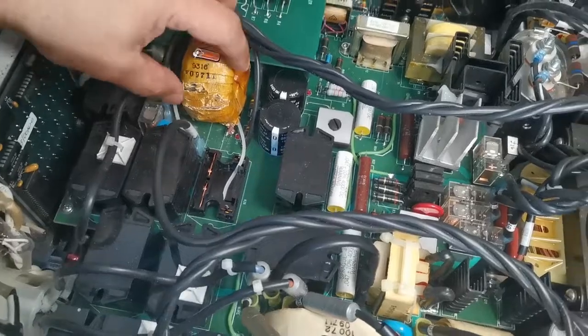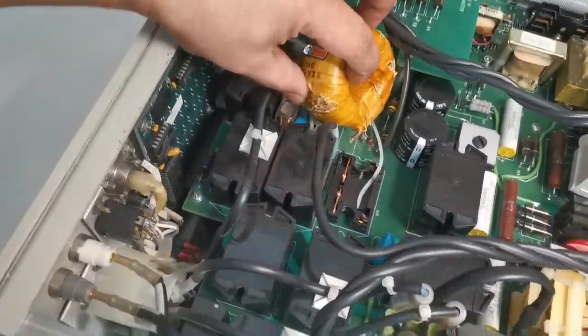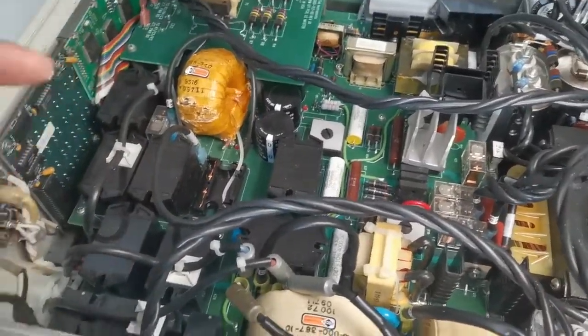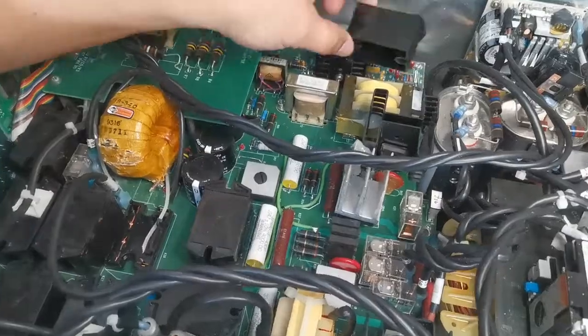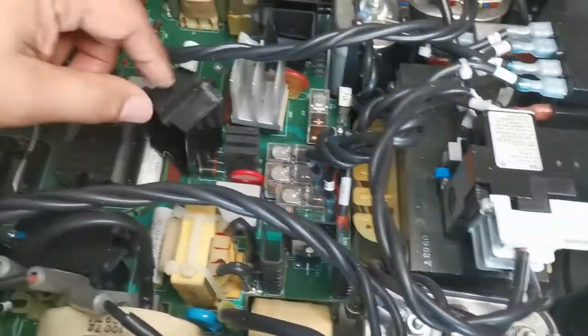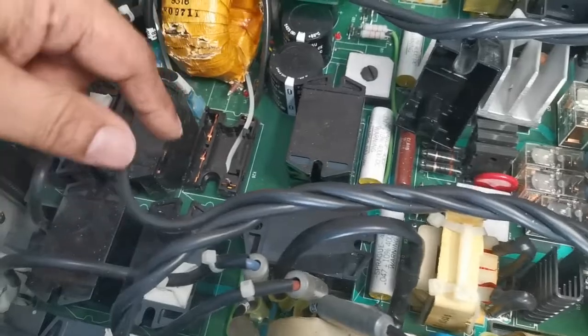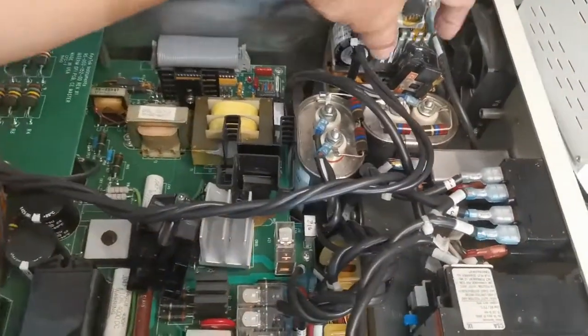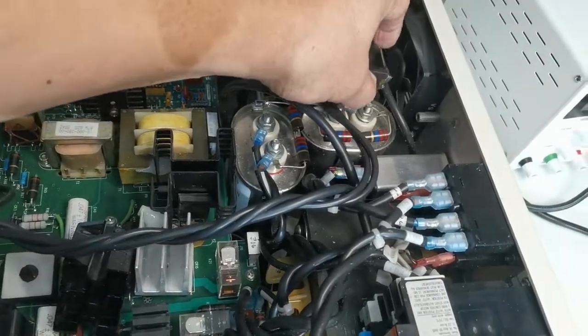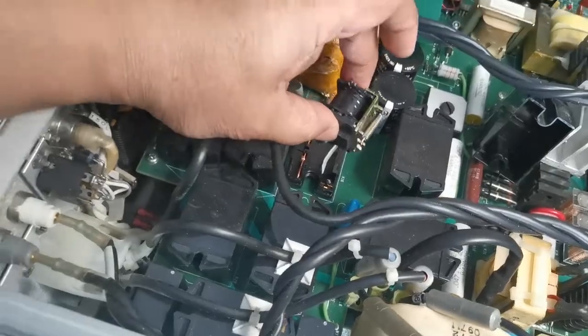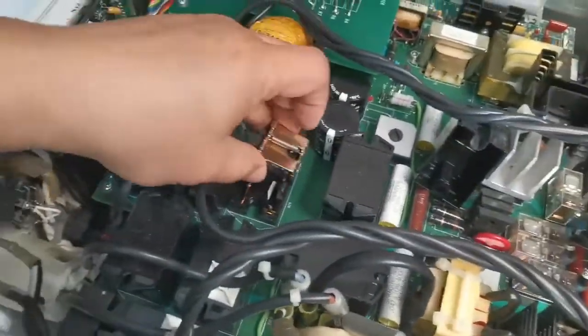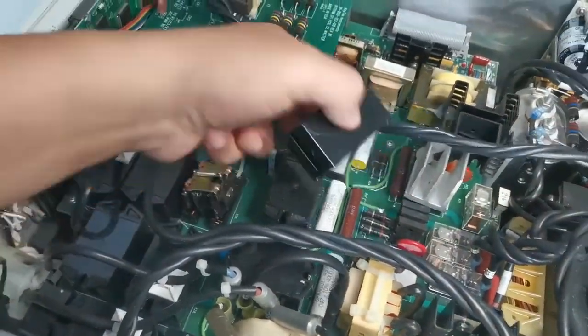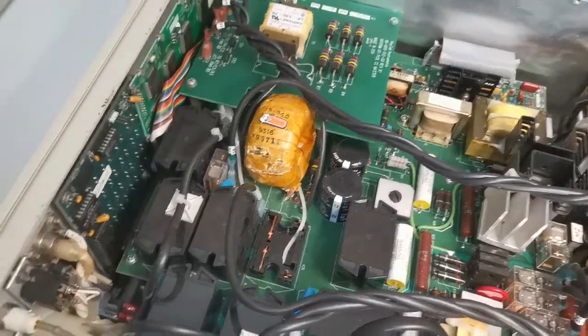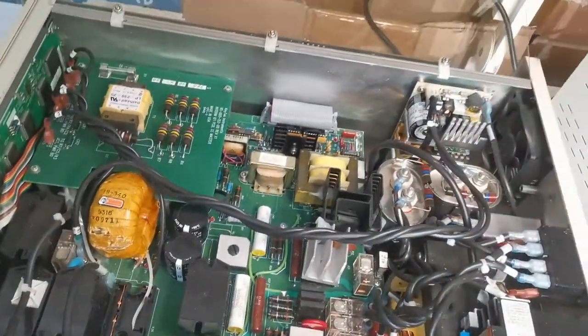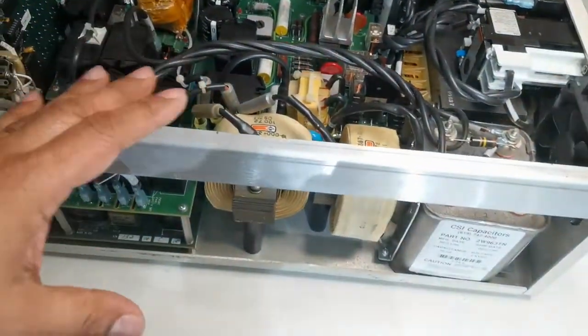So we can see that this coil here, I think this was damaged during the transport, or because it says it's not working. And this relay here is damaged, that relay. So where is the contactor here? Oh, here we go, here it is. Okay, so must be somewhere here. This is fitted like this with the relay cover. Okay, we'll just put this one aside.